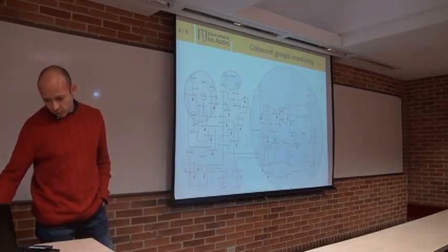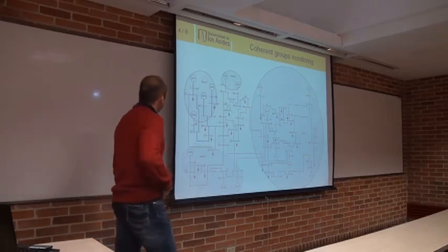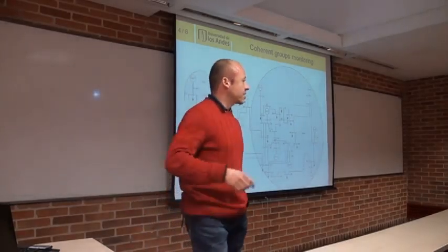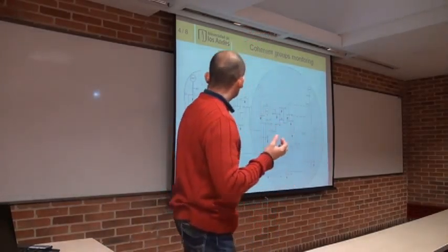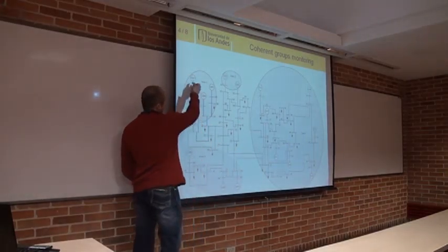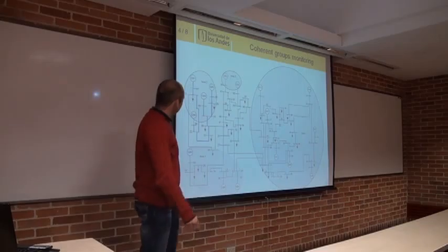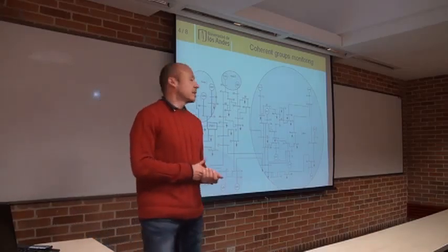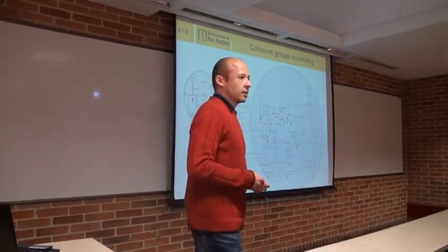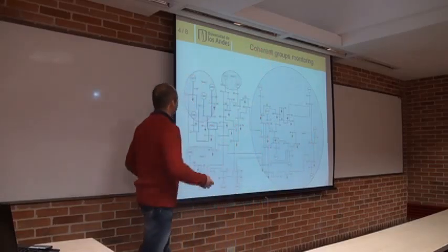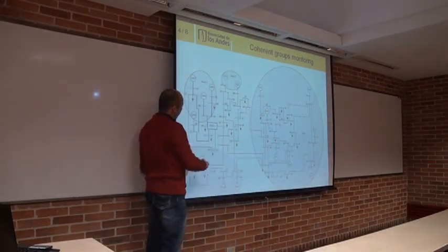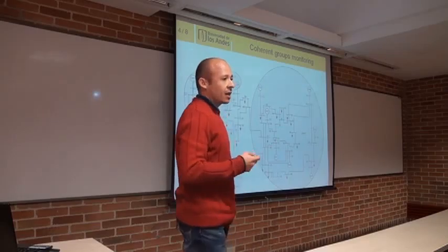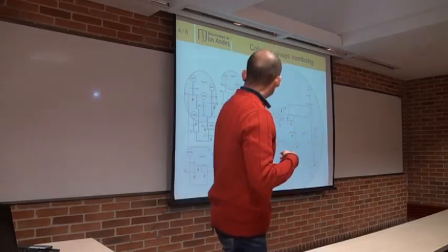After the coherent groups are found, we have to find a small network that interconnects those generators. As you can see in the figure, we have a set of transmission lines that interconnect those generators. That is the second stage to locate the first PMU. We have to find how those generators are connected. We have to find the central vertex in that set of generators and locate a PMU to monitor that group.